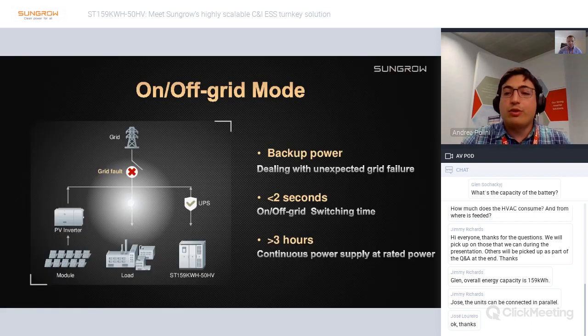Our ESS can also be used to guarantee business continuity and power generation continuity in the event of a power outage. In case of a grid fault, the protection relay protecting the customer load will open. However, the ESS will stay on thanks to the UPS built into the battery connection panel. When the local controller gets the signal that the installation has been safely disconnected from the grid, it will enter off-grid mode in less than 2 seconds.